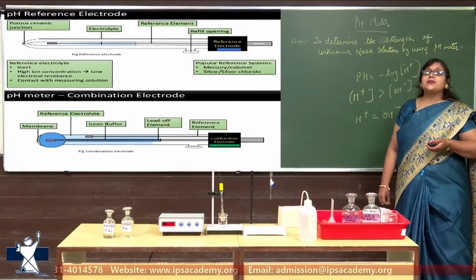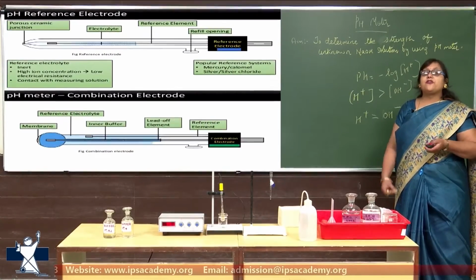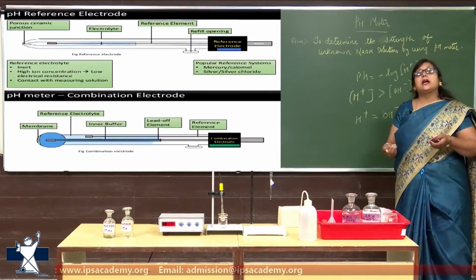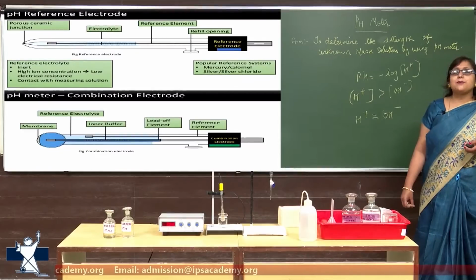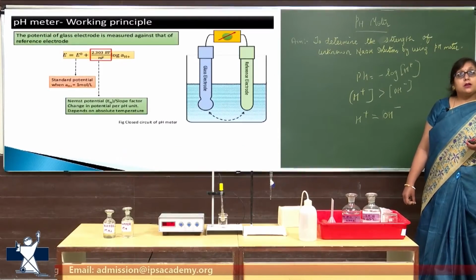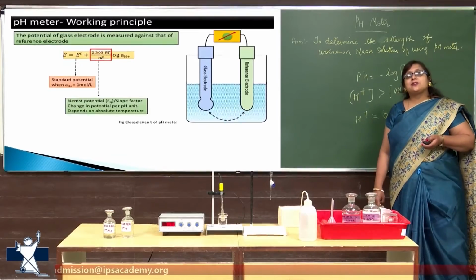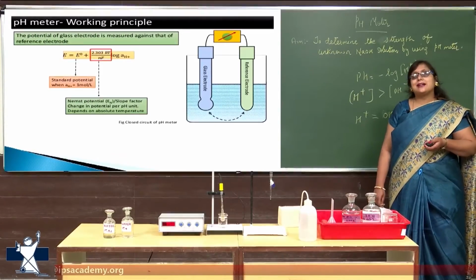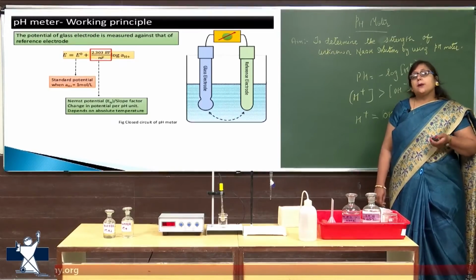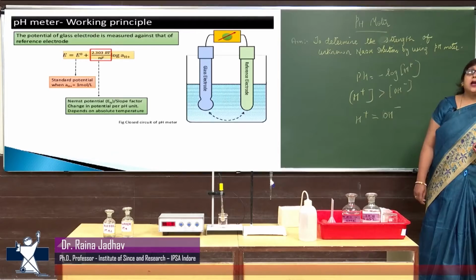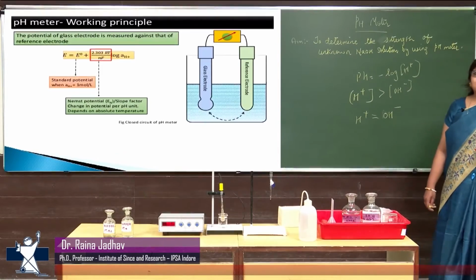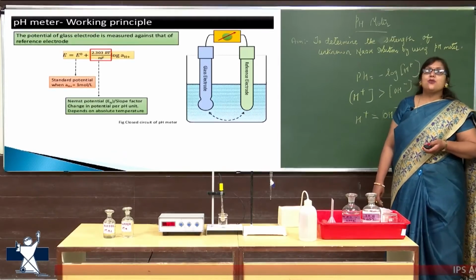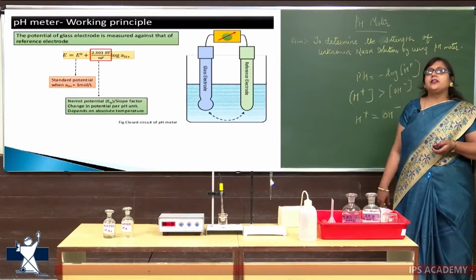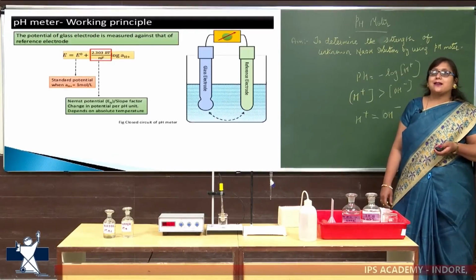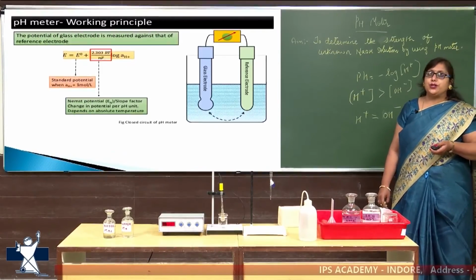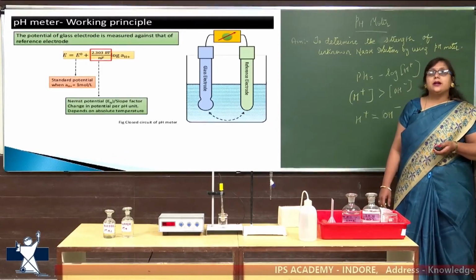Now, the latest that we are using is the combination electrode. A combination electrode is made up of two electrodes: the glass electrode and the reference electrode are combined together in one electrode system, which is known as the combination electrode system. How does the pH meter work? The potential of the glass electrode is measured against that of the reference electrode using the equation E = E0 + 2.303 RT/nF log aH+, where E0 is the standard potential and 2.303 RT/nF is the Nernst potential, that is the slope factor, the change in potential per pH unit we can measure, and it depends upon the absolute temperature.